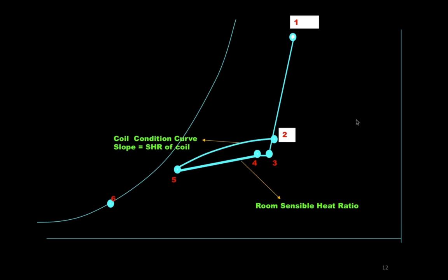Now, when we throttle the chill water flow, think about it. The large cooling coil now receives less chill water flow, and that makes the surface temperature of the coil rather warm. The warmer the surface temperature, the less dehumidification occurs on the coil surface. And that's exactly what I show on this slide.